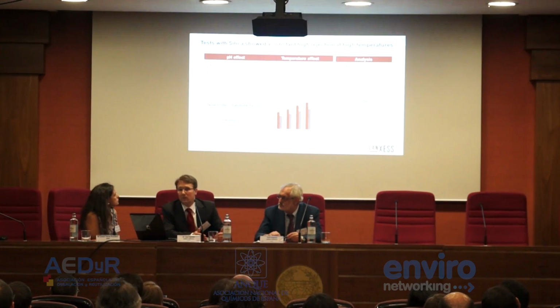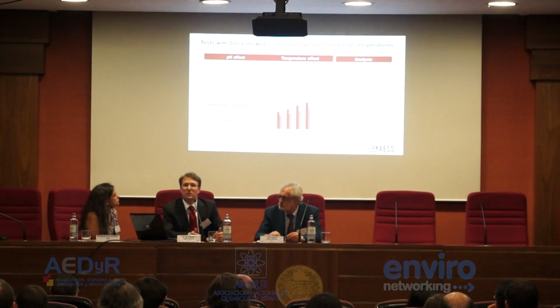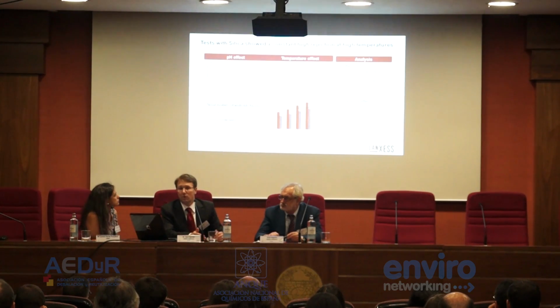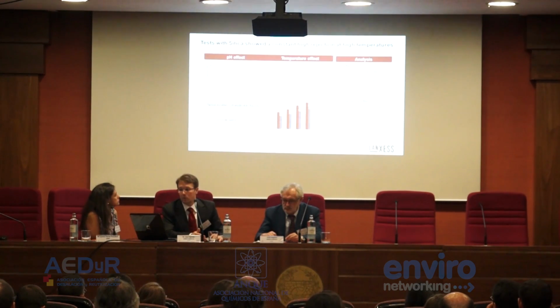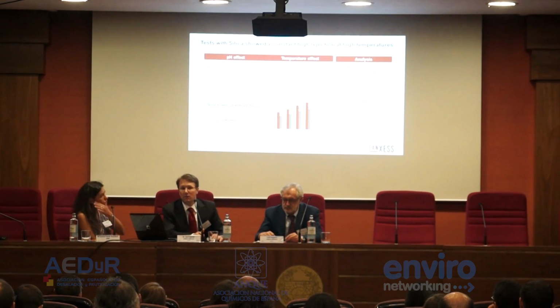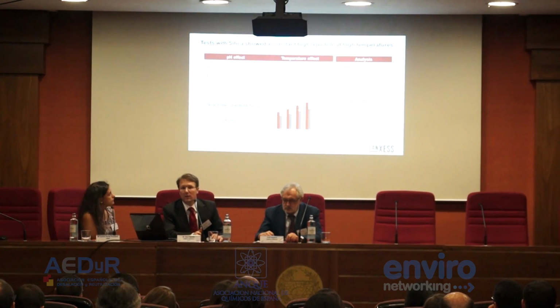We have of course taken into account that the other membrane had a lower flux at higher temperature, and therefore it has of course an influence on the rejection. We're going now to repeat this experiment at the same flux values to support that we have here a higher rejection, but at least you can see that we have a very nice consistent rejection also at changing temperatures.